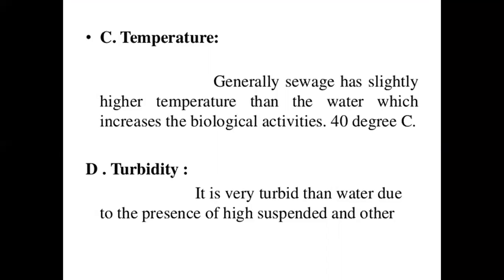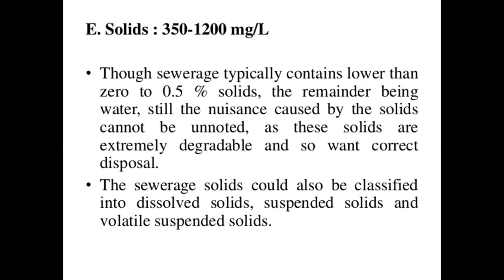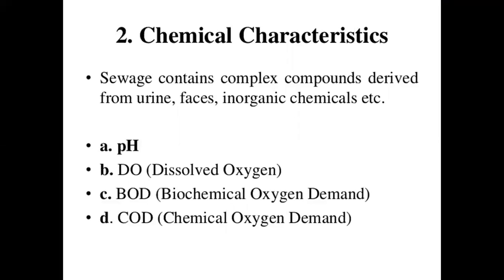Temperature: generally sewage has a slightly higher temperature than water, which increases biological activity. Biological activity is optimal around 40 degrees Celsius; normal water temperature is around 27 degrees Celsius, but wastewater temperature is around 40 degrees Celsius. Turbidity: sewage is very turbid compared to water due to the presence of high suspended matter. Solids range from 350 to 1200 mg/L. Sewage solids can be classified into dissolved solids, suspended solids, and volatile suspended solids.